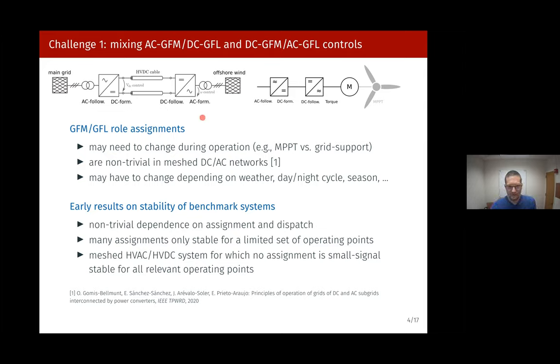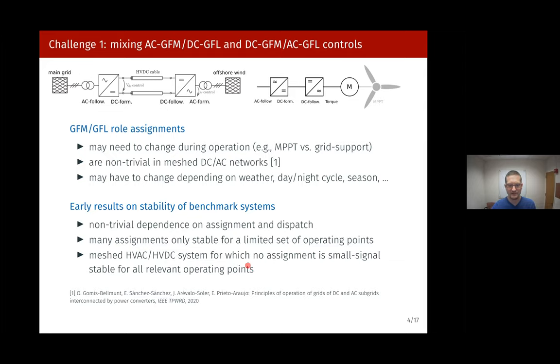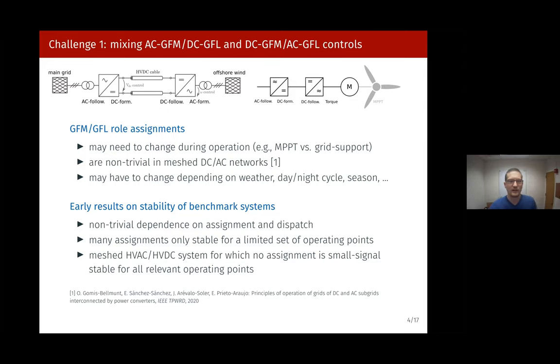In a large-scale system with many converters, there are actually many role assignments that result in an unstable system for most operating points. In systems mixing AC and DC, there are examples where it's impossible to find any single role assignment that keeps all relevant operating points small-signal stable. This means you may have to redefine converter roles in real time as operating points shift, which is a major challenge for operating future power systems.